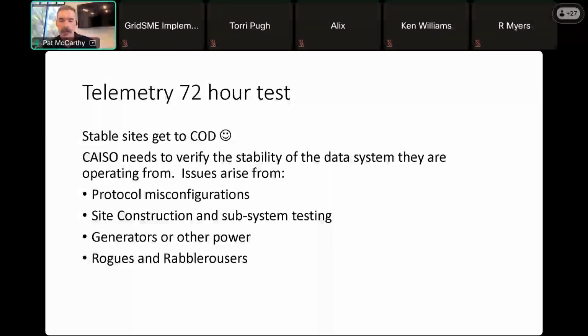So what else do I got in here? Opening breakers to perform electrical connections within the substation. That opening breaker, losing power, can cause devices to drop out, lose communications. The CAISO will see. Likewise, your generator that's on site before you've got backfeed power might just run out of gas, and you're gonna fail your 72-hour test. Or you have the type of people that are like a bull in a china shop. They come into a point-to-point test just thrashing around, making everything work in just enough time to get through the point-to-point test, and then that wasn't actually how you built your site. You've got to put everything back the way it belongs, and then things don't work. That's another big reason. That's the rogues and rabble rousers bullet at the bottom.